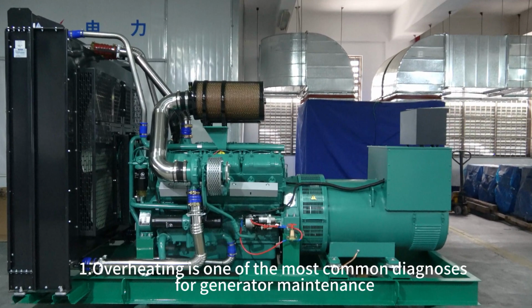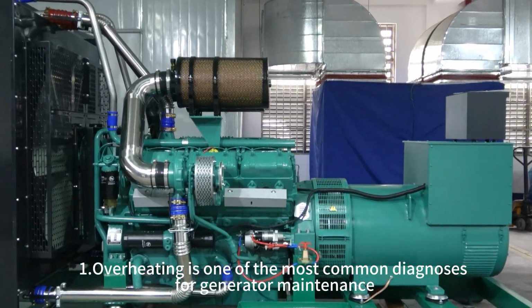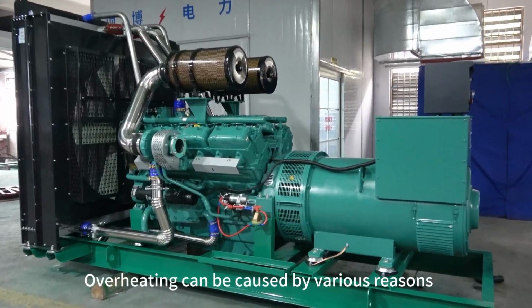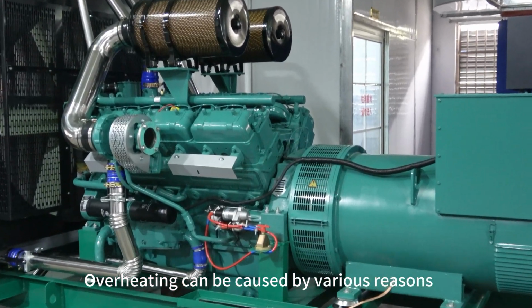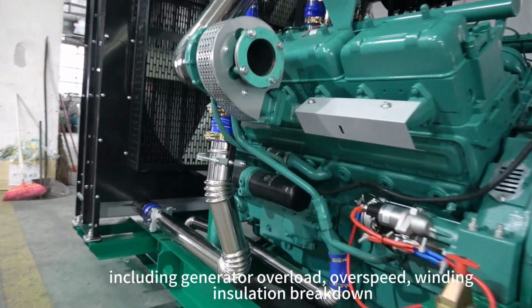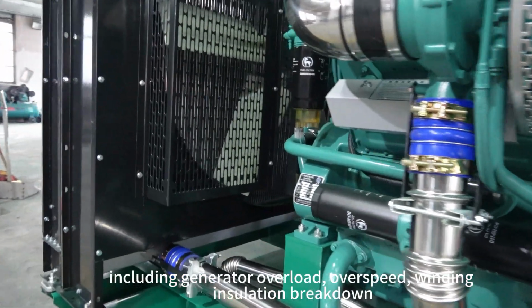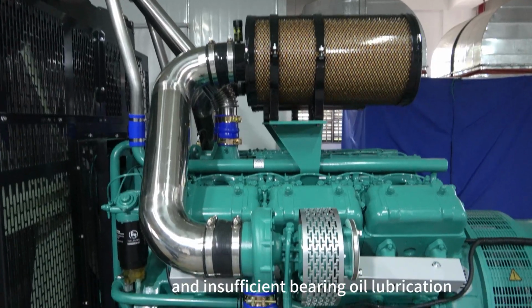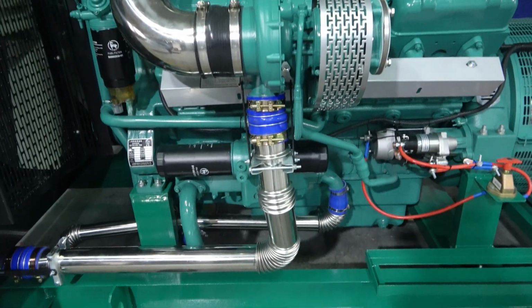Overheating is one of the most common diagnoses for generator maintenance. Overheating can be caused by various reasons, including generator overload, overspeed, winding insulation breakdown, and insufficient bearing oil lubrication.